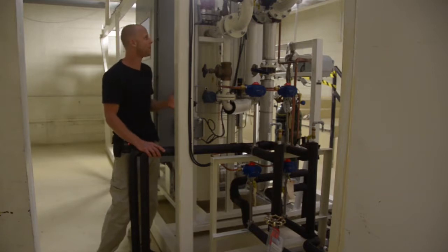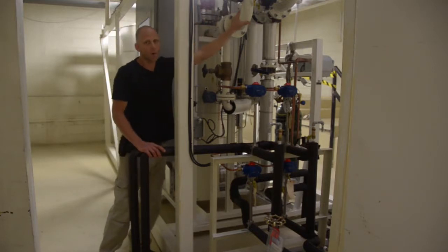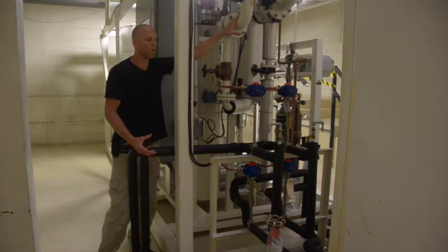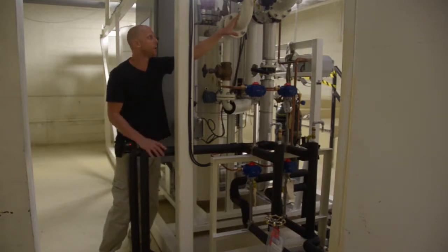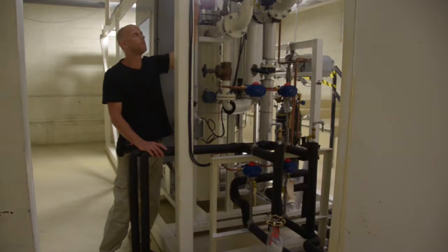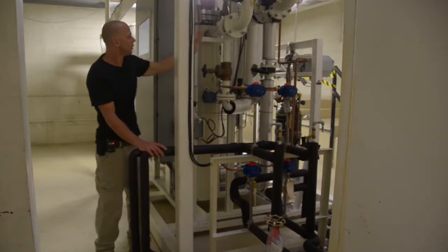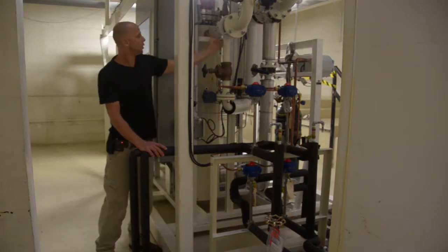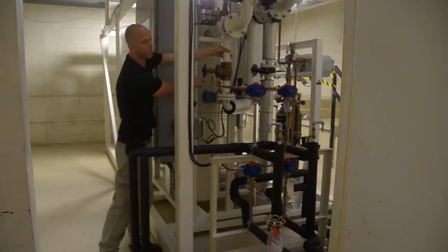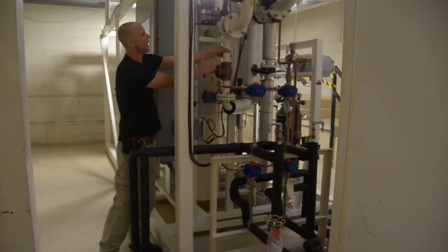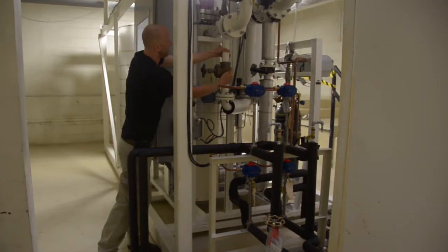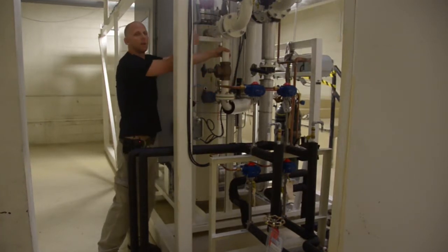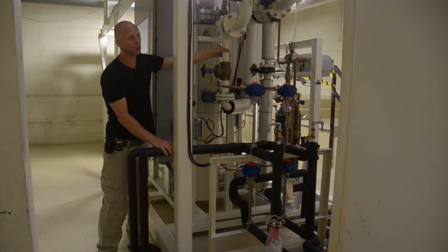It's clean and dry. But when we first start our plant up, if our plant's been down for a few weeks and it has no liquid, or we're first commissioning our plant, we don't have a supply of nitrogen. So what we do is we use this startup valve, V365, to take some of the incoming process air in a short cycle bypass line, and we take that air and we put it into our heater. That's as an initial regeneration process.